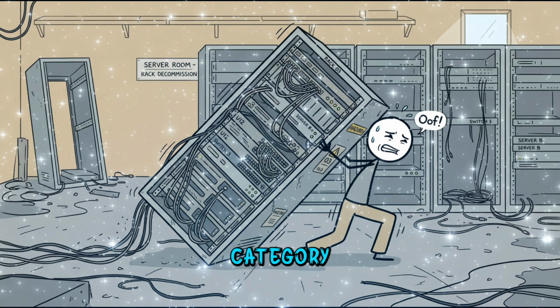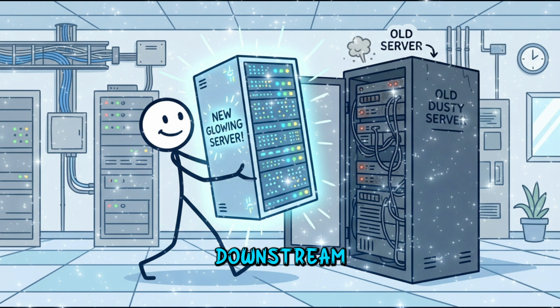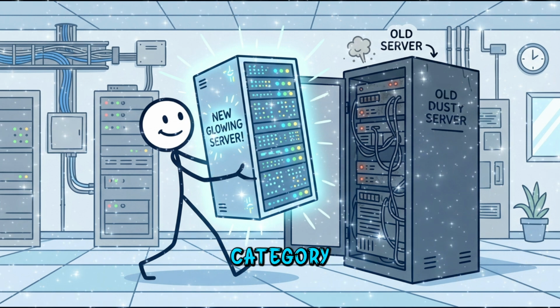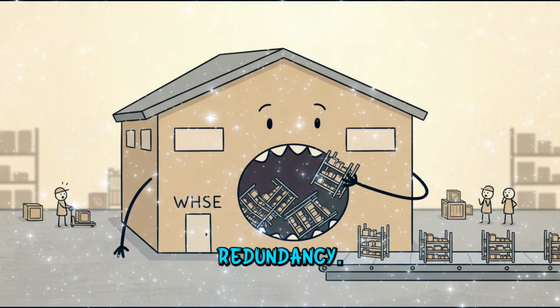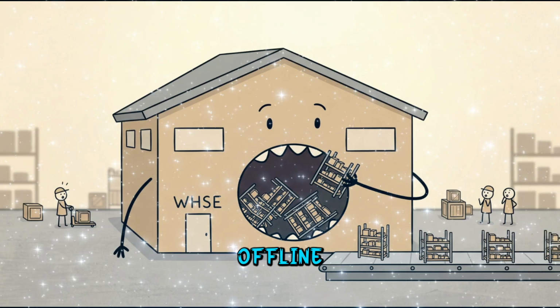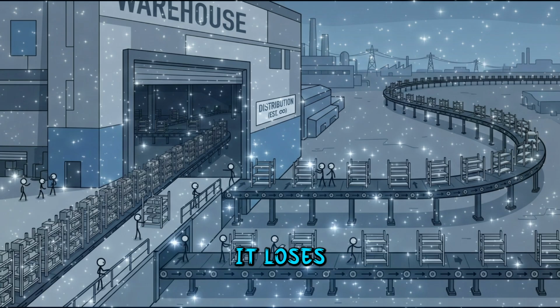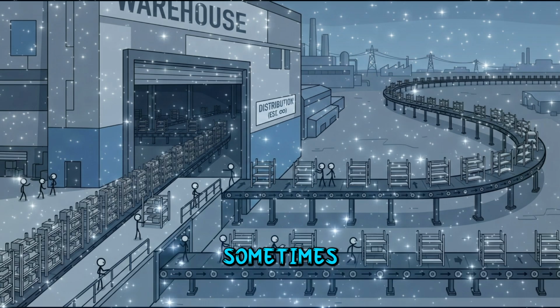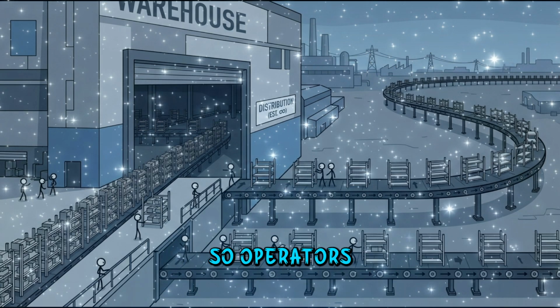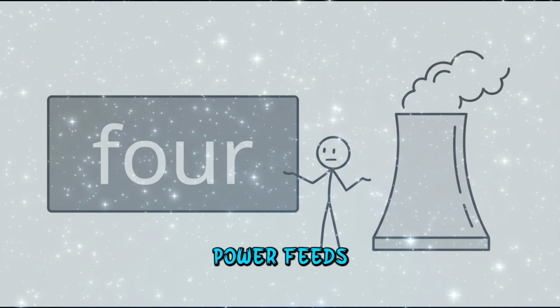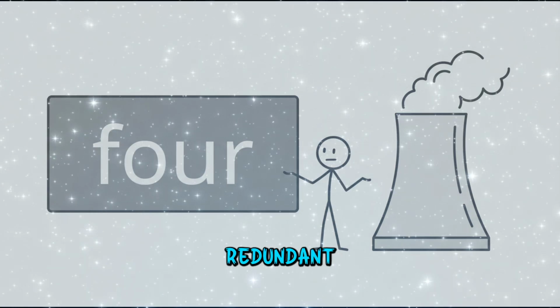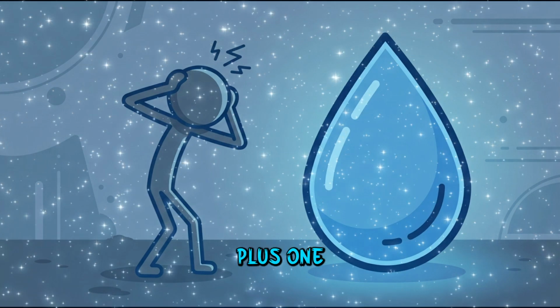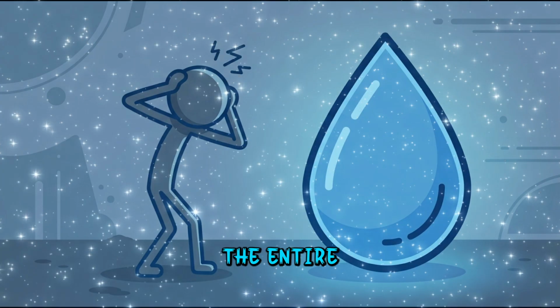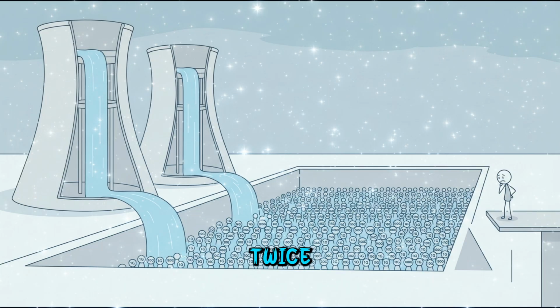Heat. Every category in this build exists downstream of managing it. Category 5, redundancy. A data center that goes offline doesn't just lose money, it loses trust, contracts, sometimes lawsuits. So operators build in redundant power feeds, redundant generators, redundant cooling loops, often rated N+1 or 2N, meaning the entire critical system exists twice, in full.